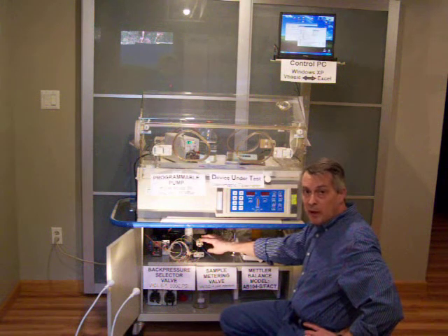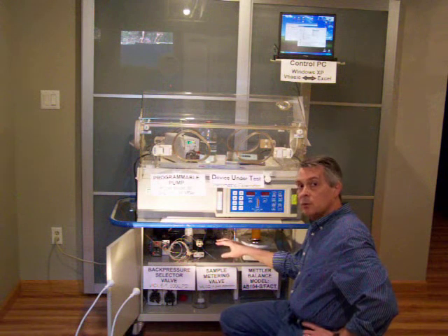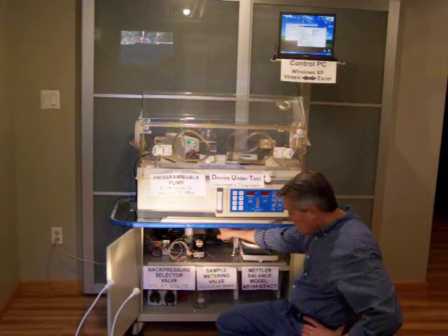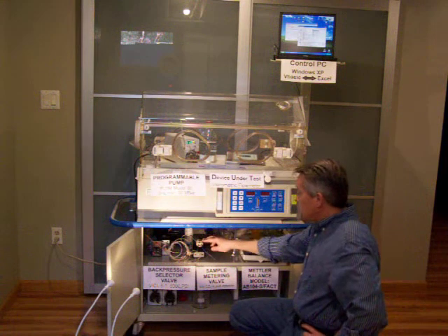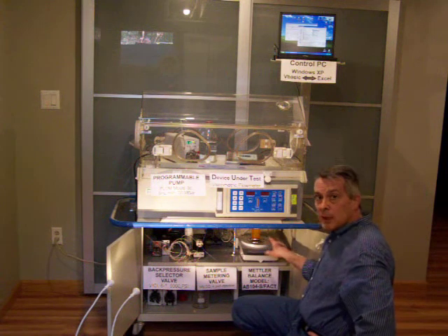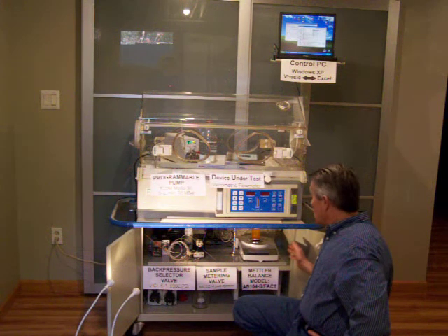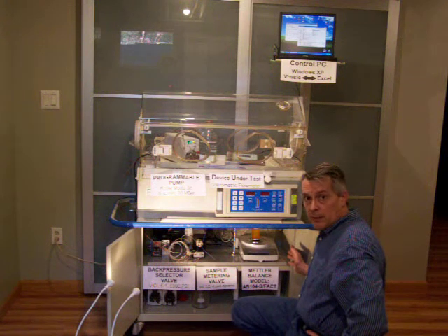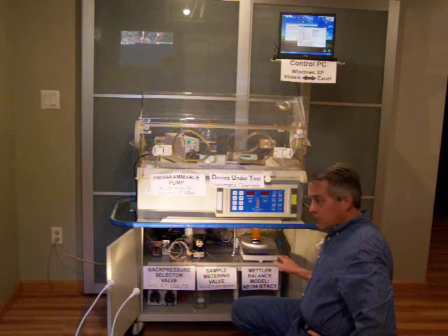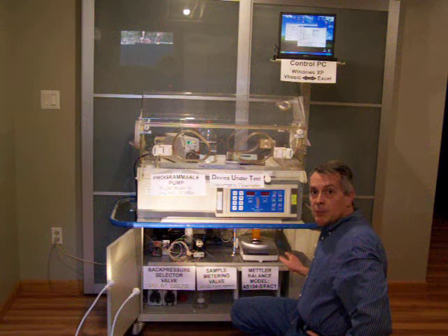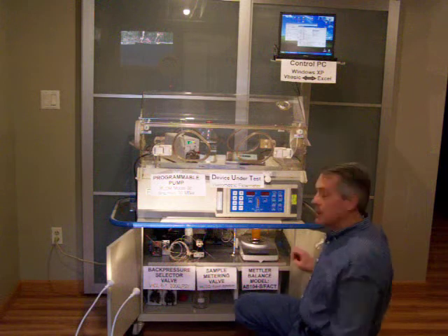The output of the sample metering valve is also controlled by the PC, although indirectly through RS-232. It's actually TTL controlled by a little programmable logic controller here in the back, which you can't see. That's also by design. That liquid is gated onto this Mettler balance, which is a very accurate, precise, and repeatable device to accumulate the flow over a given period of time. Flow over time, of course, is the definition of flow rate. The resolution of this device is 0.1 milligrams out of 100 gram capacity.